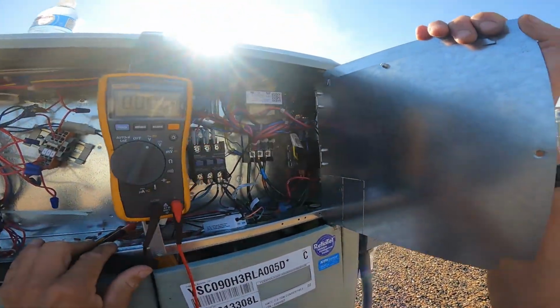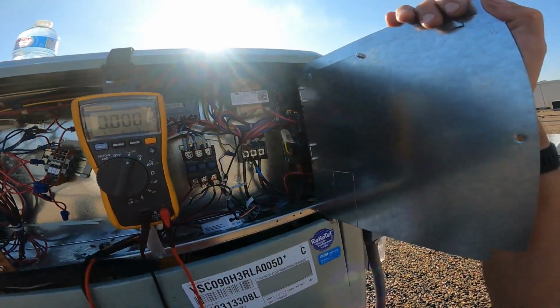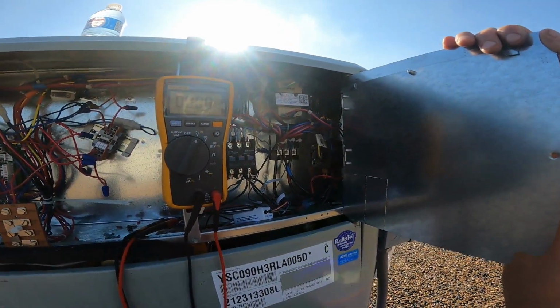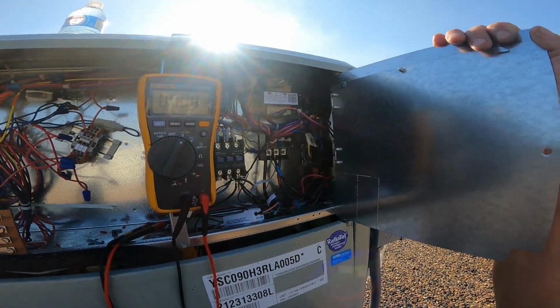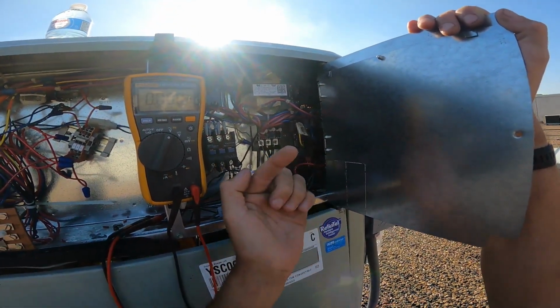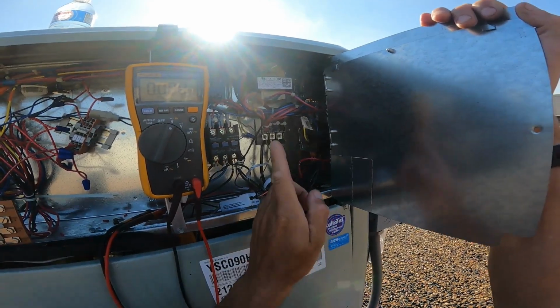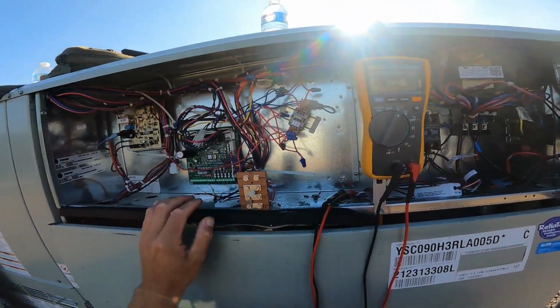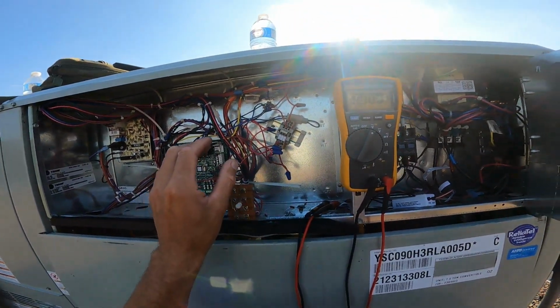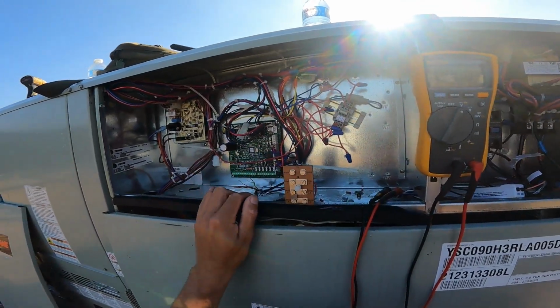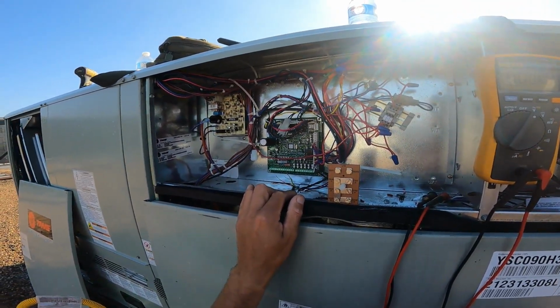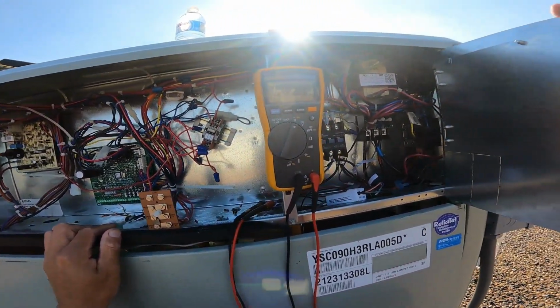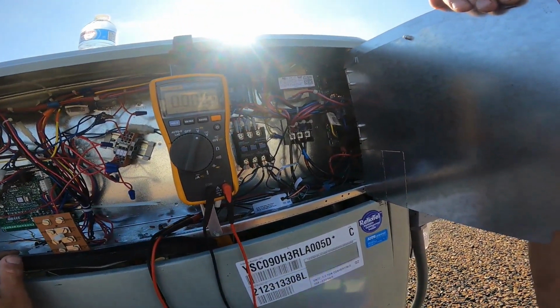So the other thing I did was disconnect the outdoor ambient temperature sensor for the crankcase heater. I don't necessarily believe, in my opinion, that we need crankcase heaters in Texas. There may be about zero days out of the year that you're going to be trying to cool your building in the dead of winter, so you shouldn't need a crankcase heater.